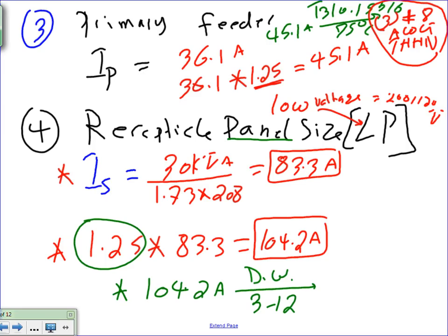Chris, what's the next standard panel? 125. Thank you. 125 amp. So no matter what, your next standard panel is 125 amp. Make sense? Now look at this. I have a 125 amp panel tied to an 83 amp 3-phase transformer. Kind of like defeating the purpose. You have more amps in the panel than the transformer, but the reason for this is continuous load. We're going to allow the continuous load of 25% on the panel. Any questions, guys? So my panel size is 125. Now we go by 125 amp, 3-phase panel.